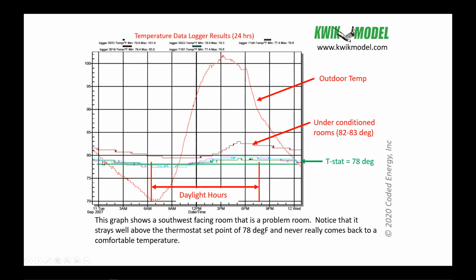And you see, even at night, so here's the daylight hours from roughly 6 a.m. to 7, 8 p.m. Even at night, the outdoor temperature gets down to 70 degrees, well below the thermostat set point. Even so, this room never cooled off, all right? Some interesting things going on here. Now, had they opened a window and let that room cool with 70 degree outside air, it would have done that. But you can't tell homeowners, oh, the only way you're going to be comfortable is if you open outdoor windows. That's not what you're designing to. You're designing so that a house can stay comfortable with the windows closed.